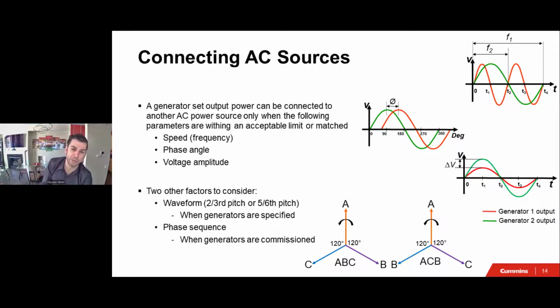We want to make sure that the winding pitch matches. If it's not, there are ways around it. The problem with a 2/3 pitch is not really a problem, but a 2/3 eliminates the third harmonic current versus a 5/6, which does not. So we want to make sure we handle that appropriately. And you only have to worry about that if you're going to a brownfield.